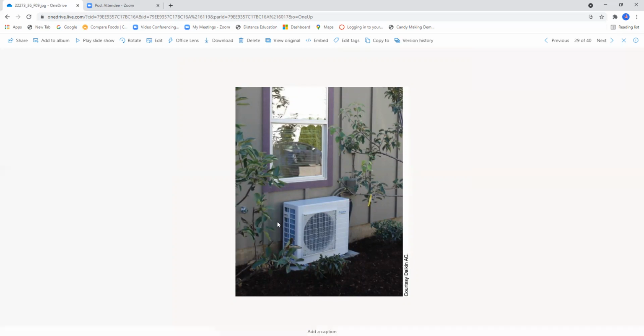The other thing you want to be able to do is wash this coil down on occasion in order to keep it operating at its peak performance. If this thing's right against the structure, how are you going to clean that coil? The only way you're going to be able to do it is to take this panel off the top and go from the inside out.